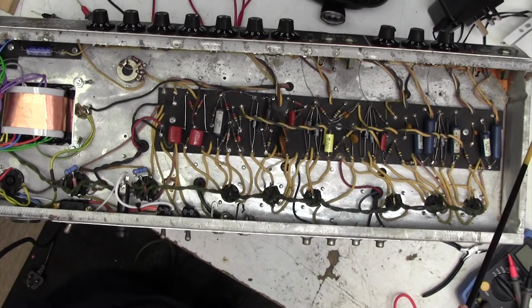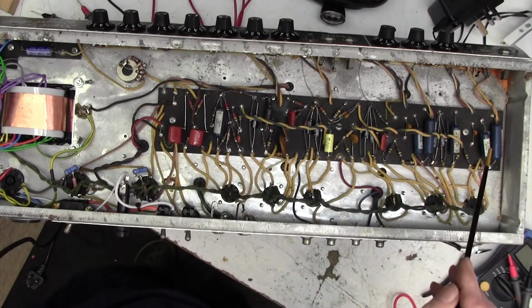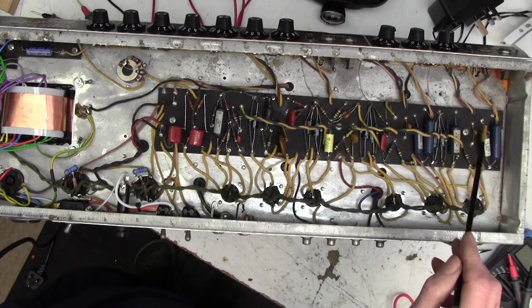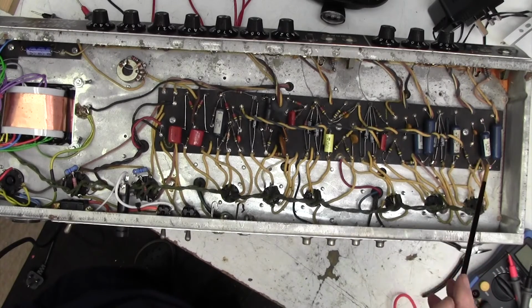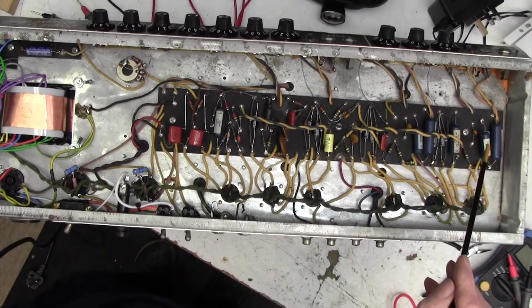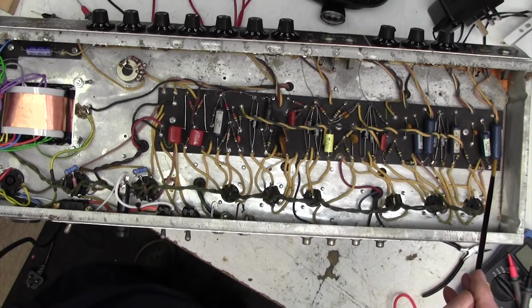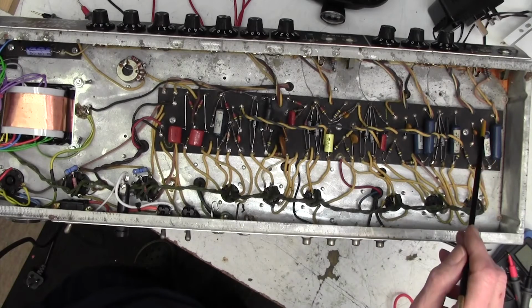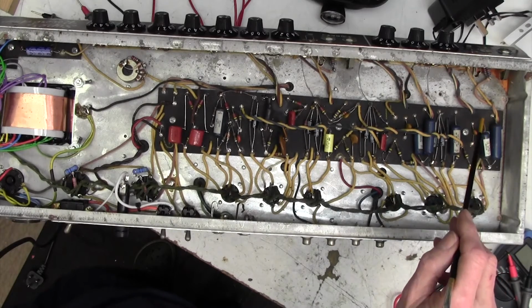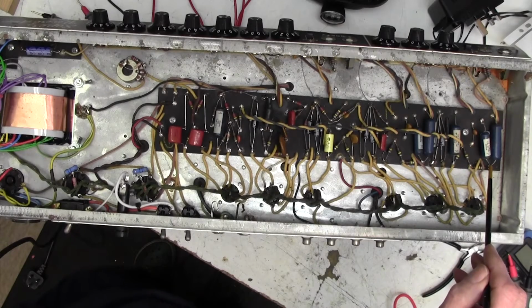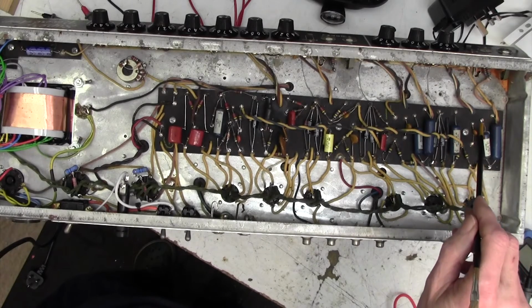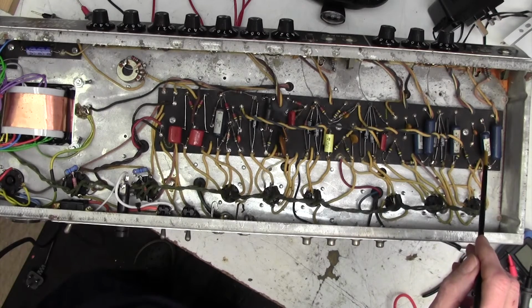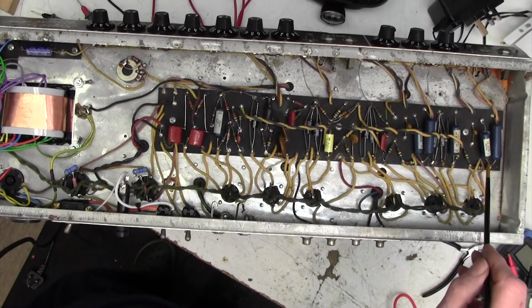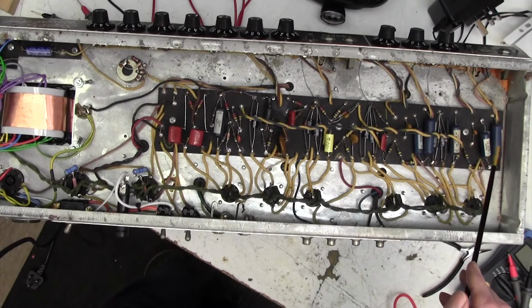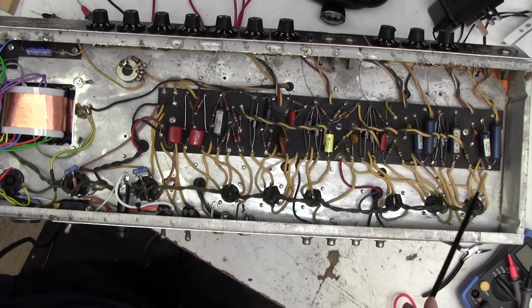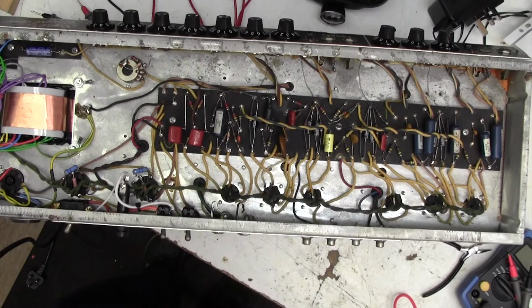What we do when we check a capacitor is check two things. We want to check its actual value, to make sure it hasn't drifted too far off, and we want to check its leakage, because these are high voltage capacitors with DC across them - maybe several hundred volts at this end and virtually 0 volts at this end. If they leak, some DC current leaks through the capacitor and ends up where it shouldn't. Unfortunately it's not particularly easy to test both of those things, but I'll show you how to do it now.